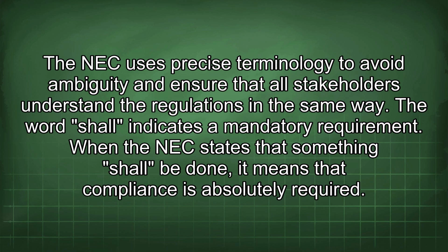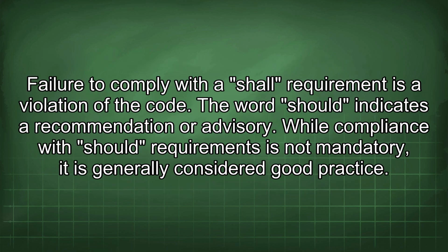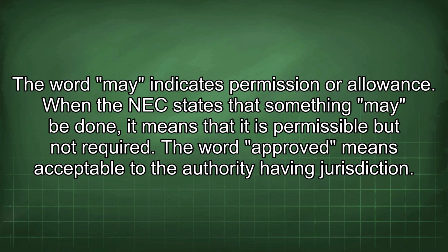The word "shall" indicates a mandatory requirement. When the NEC states that something shall be done, it means that compliance is absolutely required. Failure to comply with a "shall" requirement is a violation of the code. The word "should" indicates a recommendation or advisory. While compliance with such recommendations is not mandatory, it is generally considered good practice. The word "may" indicates permission or allowance. When the NEC states that something may be done, it means that it is permissible but not required.